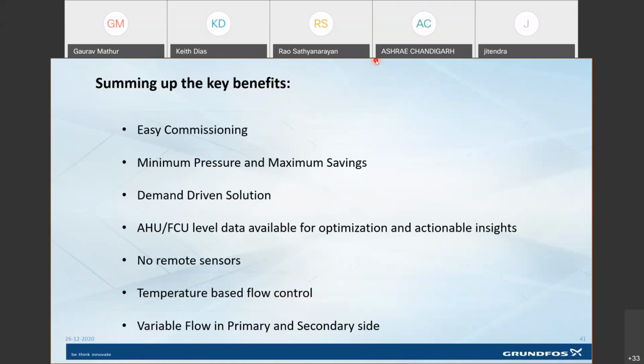The last but not the least: if you have a variable flow in primary and secondary side, and both primary and secondary side control are based on temperature, then this variable flow is the most optimum way. If you have a system where one side is pressure-based and the control of the other pumps is on temperature, then the kind of optimization possible is limited. So these are the key benefits which we see, and these are the benefits which directly connect with digitalization. And I said in the beginning that digitalization is all about change in the culture, the way we look at our systems in the buildings and not just the equipment.